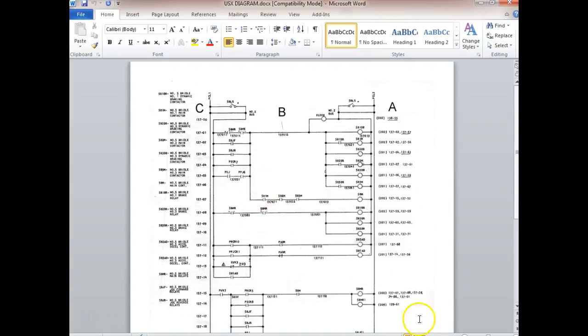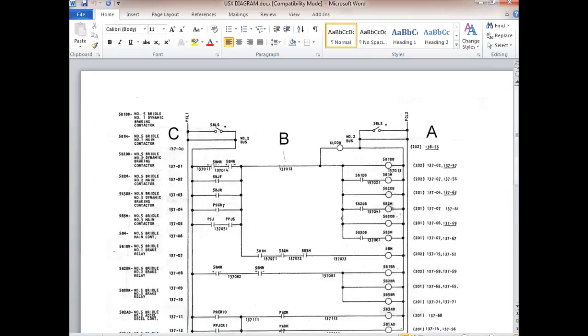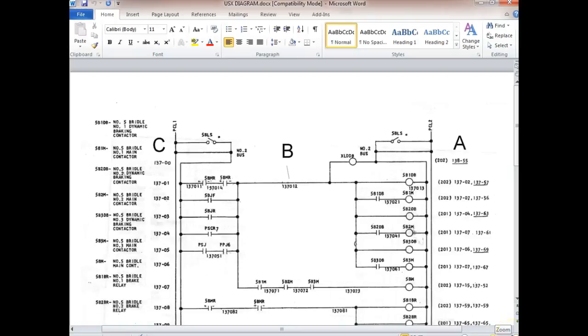Do you see any relays on here labeled M? No, but they're given names according to what they do. Over a while you'd pick up names like 5B, number 5 bridle, number 1 braking, dynamic braking relay. After working on this, you'd pick up these names. What they do is give a mnemonic, a memory jogger, so I know any contact that belongs to this relay will have the same name.